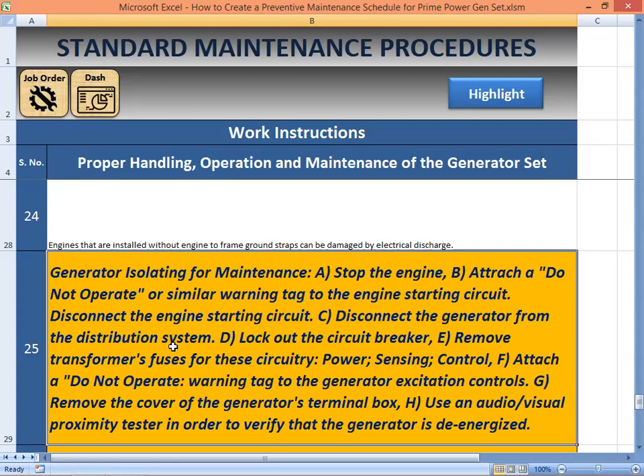Okay, disconnect the generator from the distribution system, lock out the circuit breaker. This is what I've said, lock out, tag out. They are like a padlock. It's not enough that you turn off the circuit breaker. You also have to padlock the circuit breaker and put a tag, lock out, tag out. Remove the transformer fuses for the circuitry in terms of the power, sensing, and control. Attach a do not operate warning tag to the generator excitation controls.